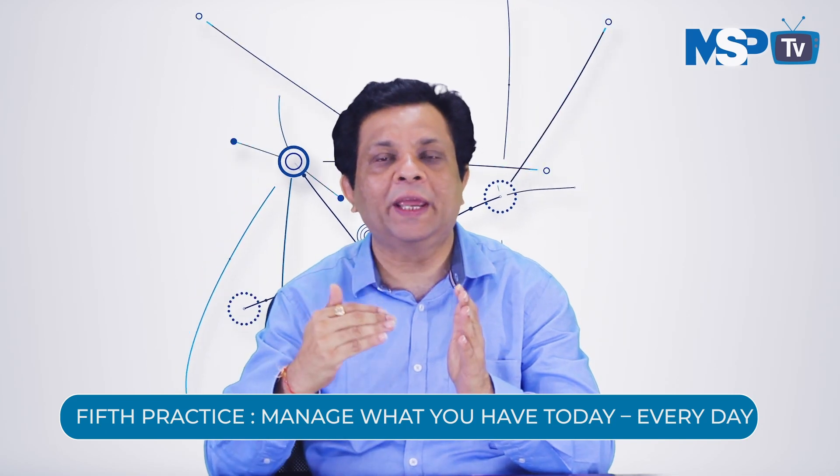Fifth practice: manage what you have today and every day. Data centers are generally designed to reach peak performance at full load, much like equipment is most efficient at peak load. But a new data center will usually not be fully loaded for years after it's built. Because designers leave room for growth, and others are seeing IT loads move to the cloud, leaving excess capacity. Whatever your case may be, your operations team has to pay attention to the actual load in your data center at any given time and manage it accordingly. If you are lightly loaded, consolidate into a certain section to conserve on cooling capacity. This is a management discipline that should be enforced daily to ensure operational efficiency and cost savings.